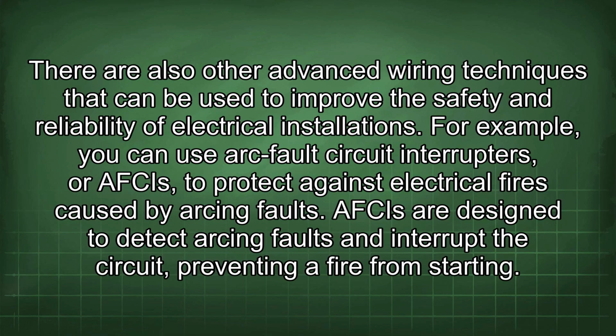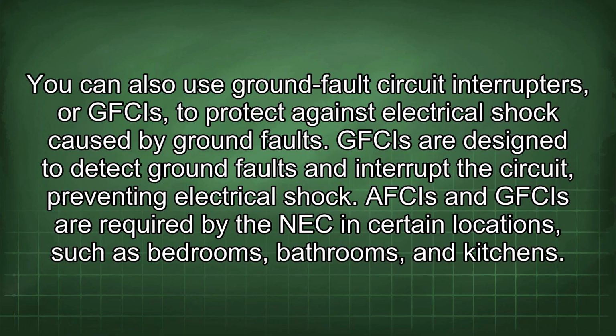There are also other advanced wiring techniques that can be used to improve the safety and reliability of electrical installations. For example, you can use arc fault circuit interrupters or AFCIs to protect against electrical fires caused by arcing faults. AFCIs are designed to detect arcing faults and interrupt the circuit, preventing a fire from starting. You can also use ground fault circuit interrupters or GFCIs to protect against electrical shock caused by ground faults. GFCIs are designed to detect ground faults and interrupt the circuit, preventing electrical shock. AFCIs and GFCIs are required by the NEC in certain locations such as bedrooms, bathrooms, and kitchens.